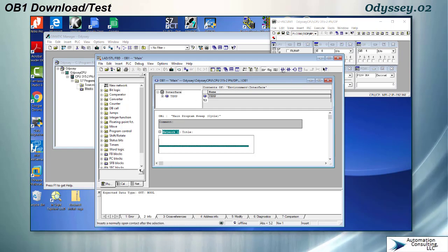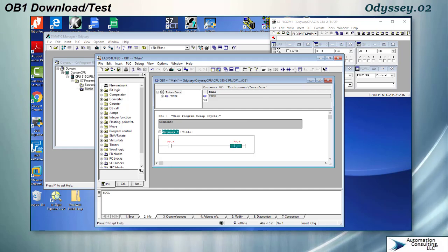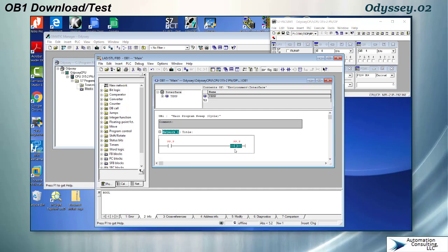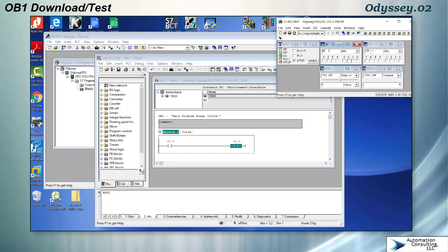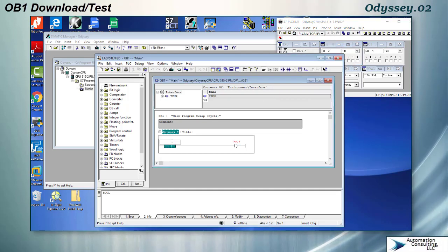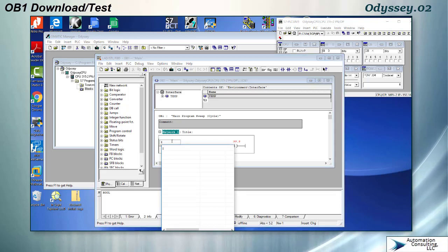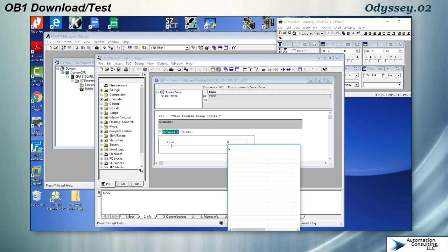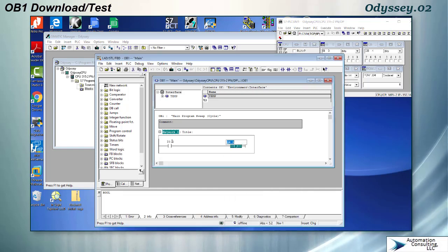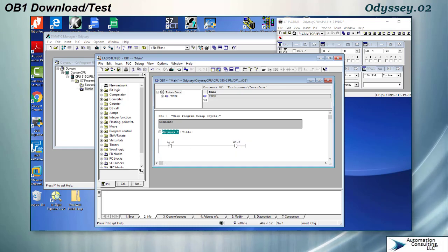We'll do a quick test here and make sure that our simulator is working properly. Simplest possible logic that you can put in a Siemens PLC. You must always have a contact and a coil in Siemens, you can't put just a coil hanging out there like you do in Allen Bradley. I'm going to use the I/O that we have here in this simulator which is I input byte zero and output byte four. I'm going to use I0.2 and Q4.3. I'm not going to name them yet, we'll save that for the next routine.